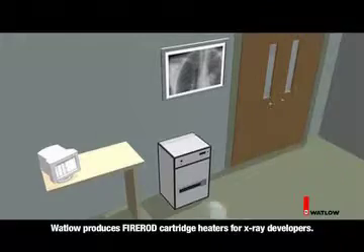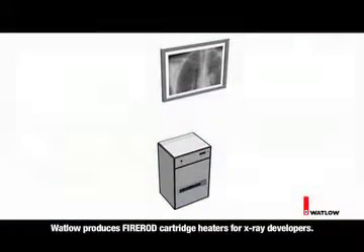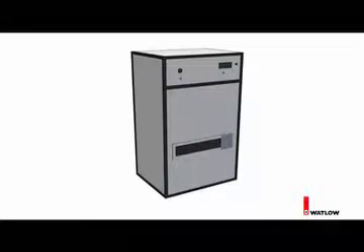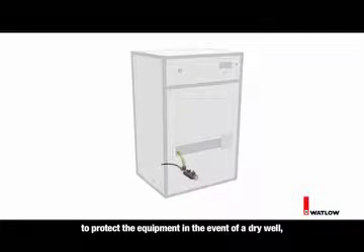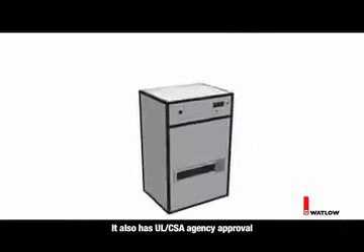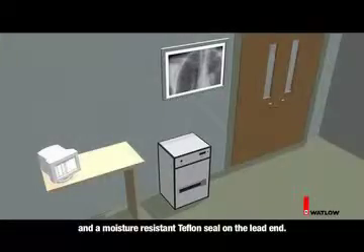Watlow produces FIREROD cartridge heaters for X-ray developers. This cartridge heater has an internal high-limit thermostat to protect the equipment in the event of a dry well, and the heater is made of 316 stainless steel passivated to eliminate contamination. It also has UL-CSA agency approval and a moisture-resistant Teflon seal on the lead end.